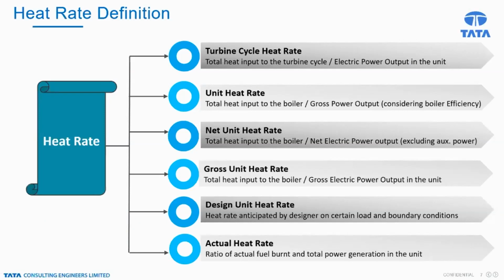So the total heat input to the turbine cycle divided by the electric power output we call the turbine cycle heat rate. Here we are excluding the boiler efficiency. The next one is the unit heat rate. Here we are taking into account the boiler efficiency, that is, the boiler is also included: total heat input to the cycle or to the boiler divided by the gross power output.